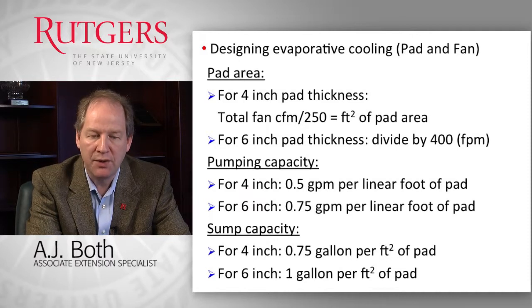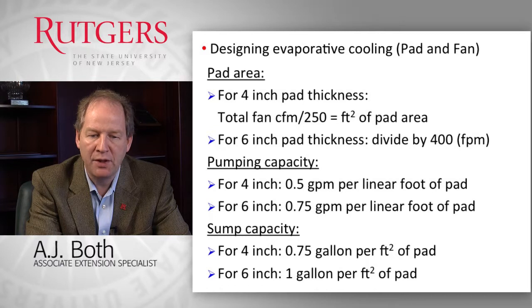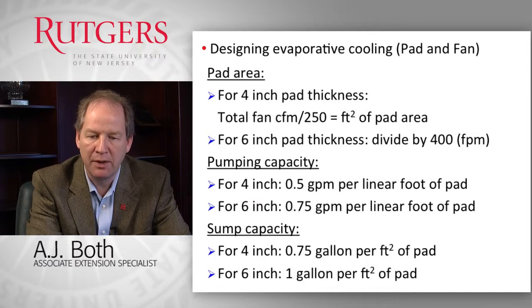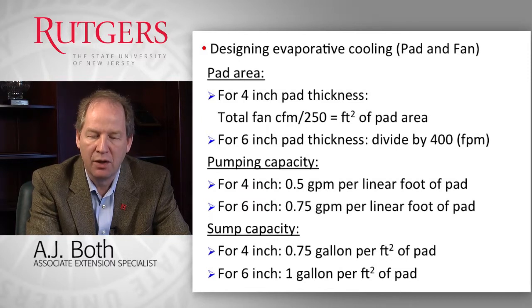The pumping capacity required also depends on pad thickness. For the four-inch pad, you need 0.5 gallons per minute per linear foot of pad. For the six-inch pad, you need 0.75 gallons per minute per linear foot of pad material. The sump or tank capacity likewise depends on pad thickness: three-quarters of a gallon per square foot of pad area for the four-inch pad, and one gallon per square foot of pad area for the six-inch pad.